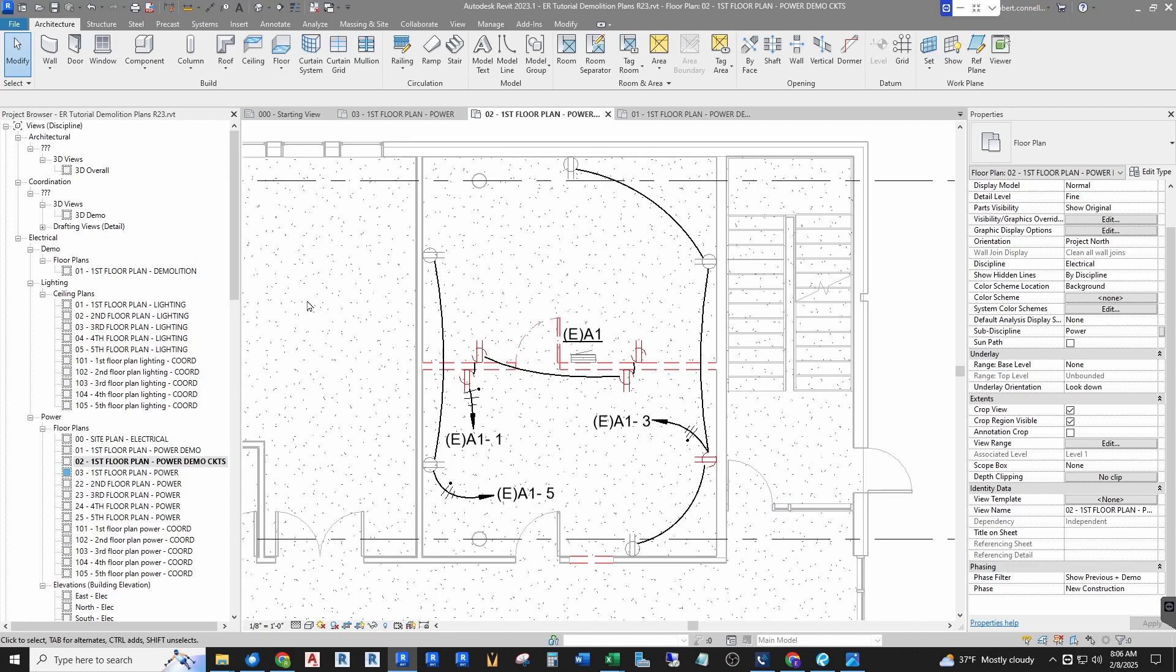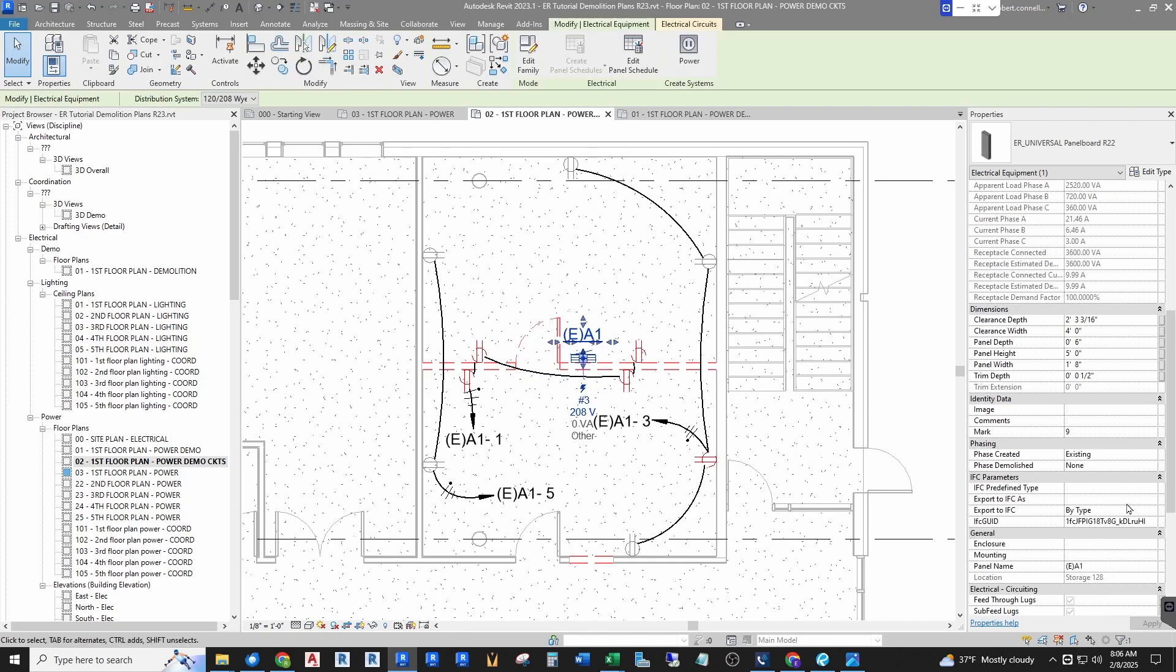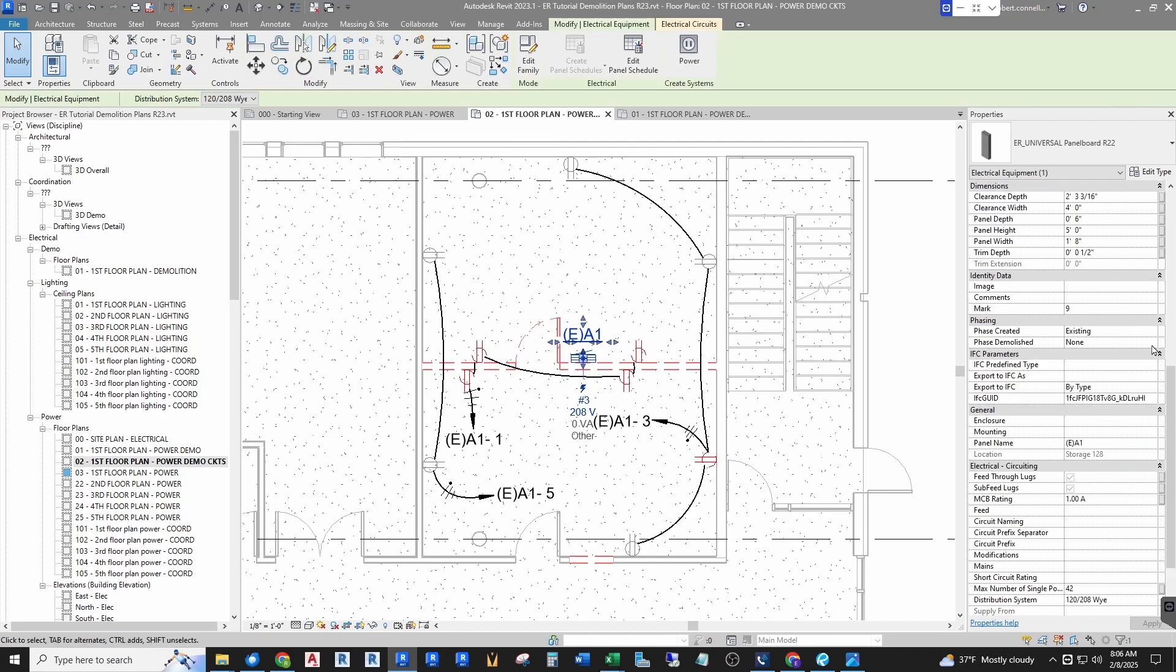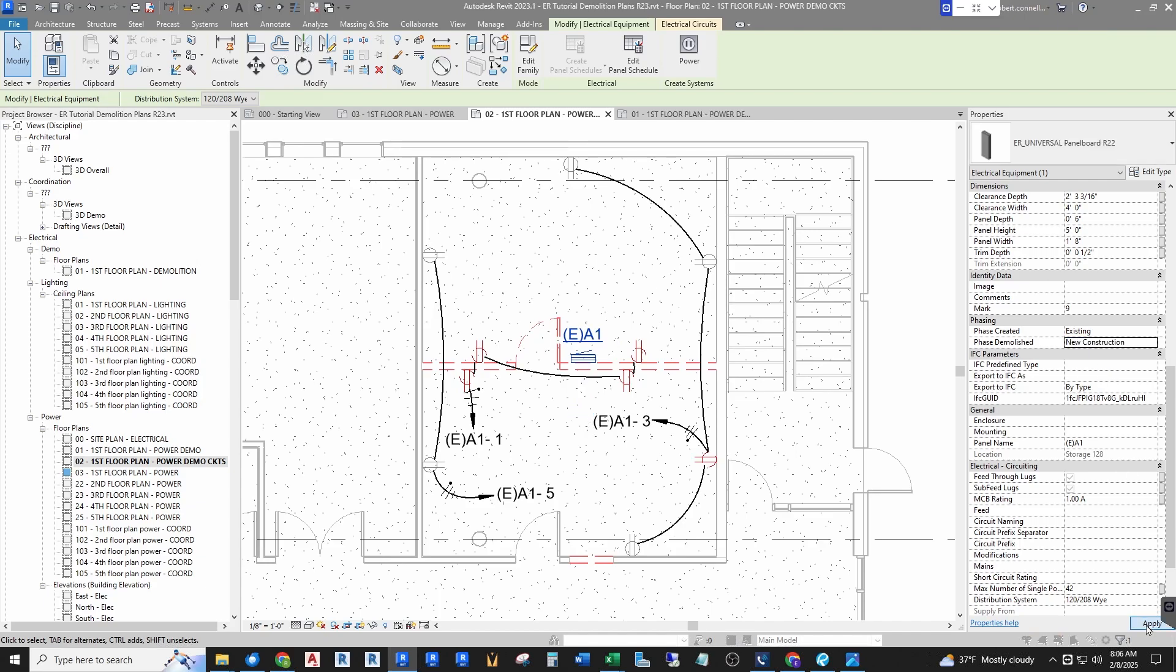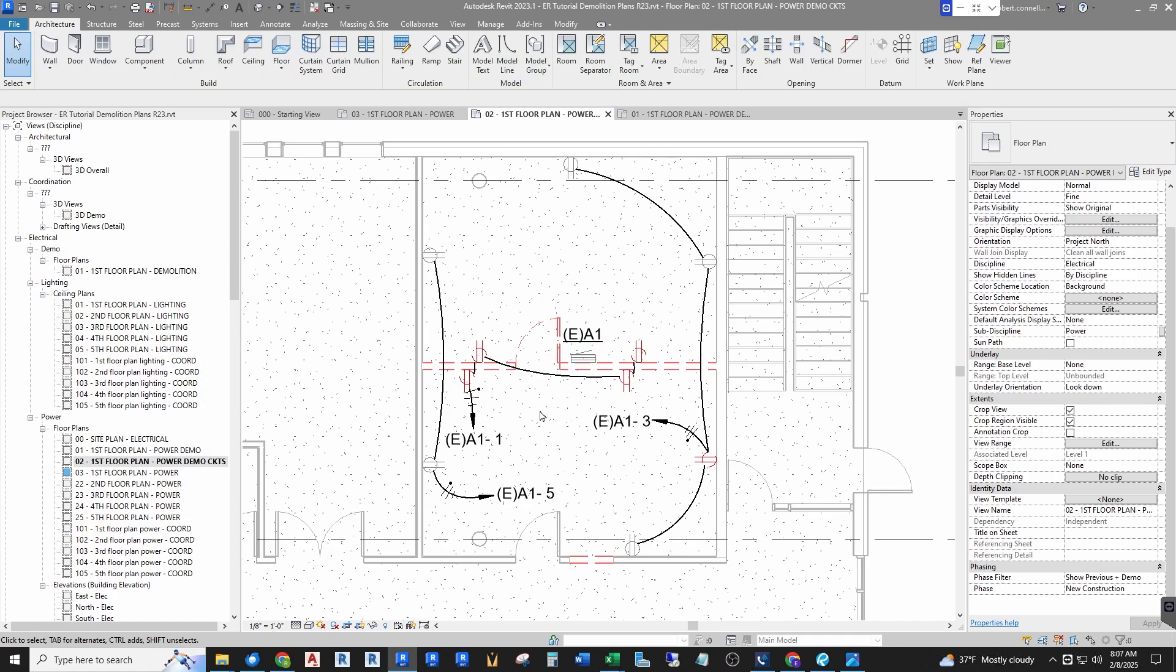Now depending on how you typically show demolition plans, some people may try to look at this plan here where I have existing circuiting shown—see how these home run back to existing panel A1. You can show it that way, but watch what happens when I demo the panel. If I say phase demolished in new construction, apply, I get lots of errors. The panel no longer matches the properties for the circuit. Disconnect the panel from the circuit. What does that even mean? And it does it for four because I have four circuits in here.